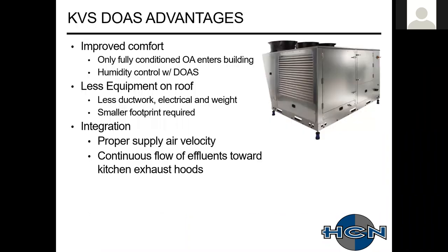So some advantages of going with the dedicated outdoor approach: you're fully conditioning that air coming in, you're lowering the humidity levels if you're using reheat options. There's less equipment on the roof because you're eliminating that dedicated makeup air unit. You're getting rid of that rooftop unit. You're getting rid of ductwork, but you're also, for the hood side of things, decreasing, because typically a lot of the exhaust only systems will have a lower exhaust rate. So you're making that ductwork smaller as well.